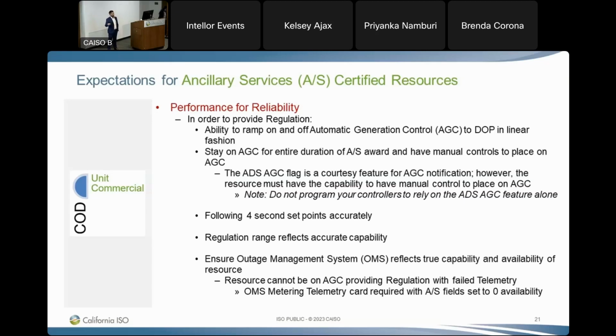A resource cannot provide AGC with failed telemetry. With failed telemetry, the resource doesn't even move, or we can't even see that it's moving, and our system says this has failed telemetry, it's on standby. So our set points don't even move, therefore it's not even providing regulation. At that time, an OMS submittal with the metering telemetry card will be submitted, and those AS fields need to be set to 0 availability. Most scheduling coordinators realize that now, but that's something that often gets missed, where they'll submit a metering telemetry but won't zero out the AS availability.